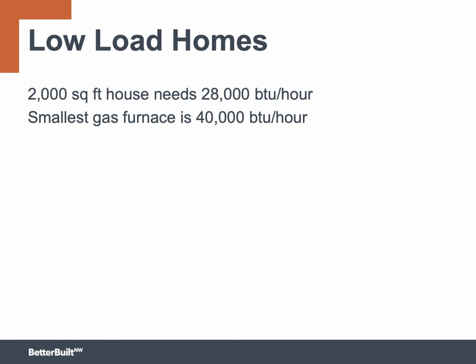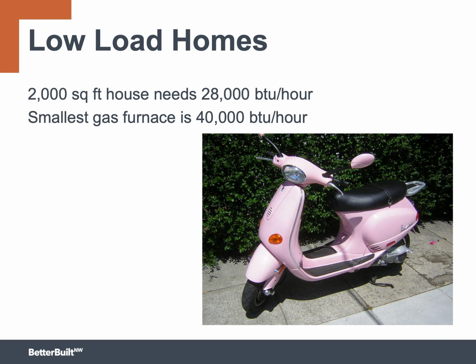One huge change is the increasing energy efficiency of new homes. The design heat load of a 2,000 square foot house built to the Energy Star standard in the Pacific Northwest is about 28,000 BTUs per hour. Few manufacturers even make a furnace below 40,000 BTUs per hour, so you're automatically putting in an oversized furnace into that house. Not only that, but there's a strong push to reduce space conditioning loads even further. New initiatives such as Passive House and Net Zero Energy need far less, perhaps 10,000 BTUs per hour. And putting an oversized furnace in a house like that is like putting a V8 in a Vespa.